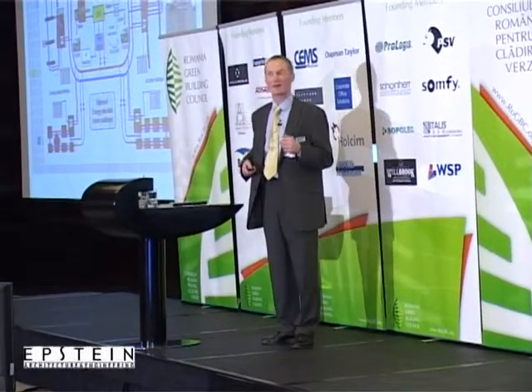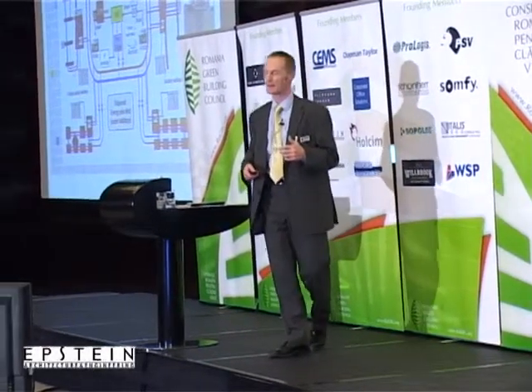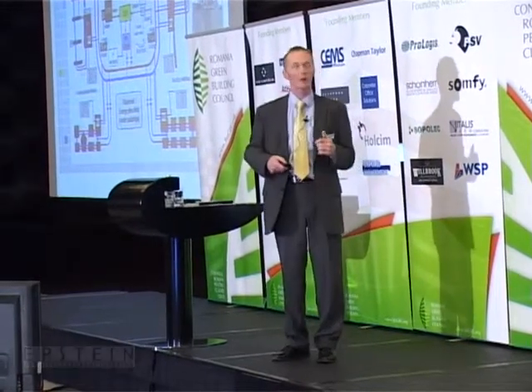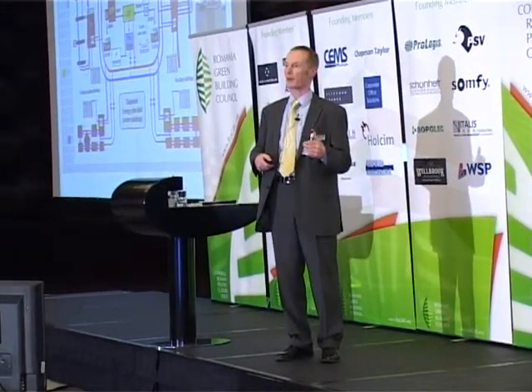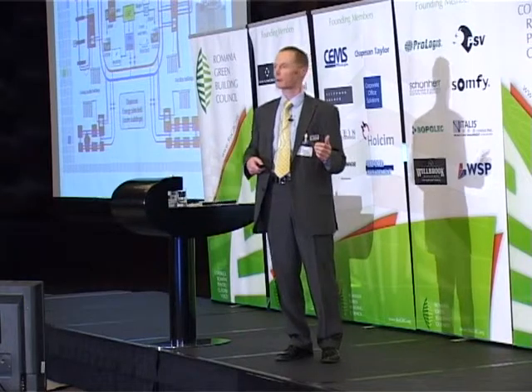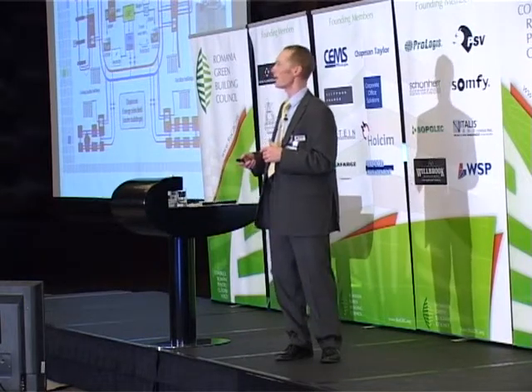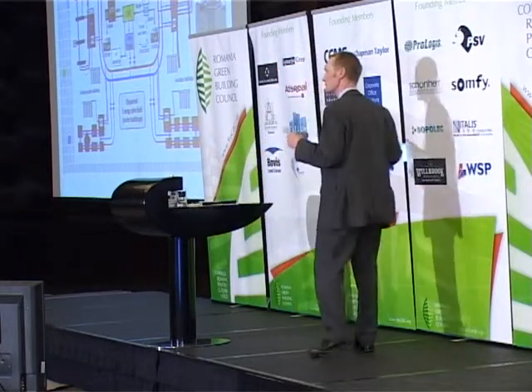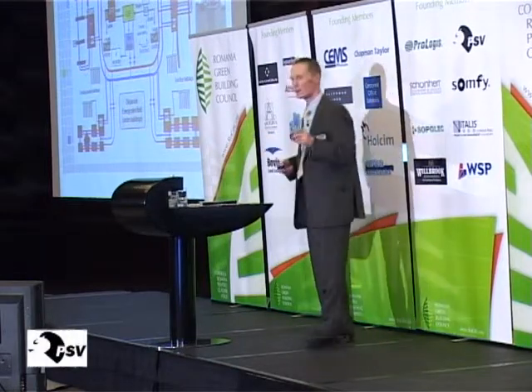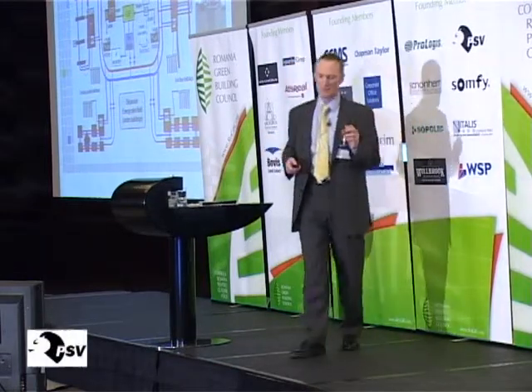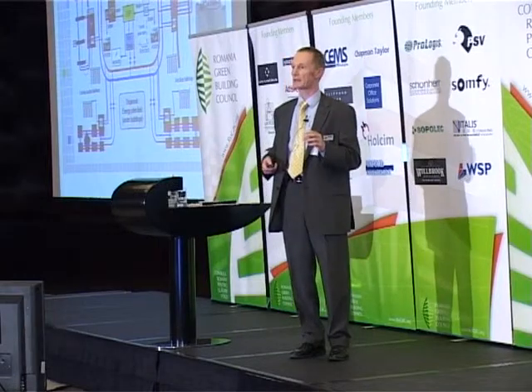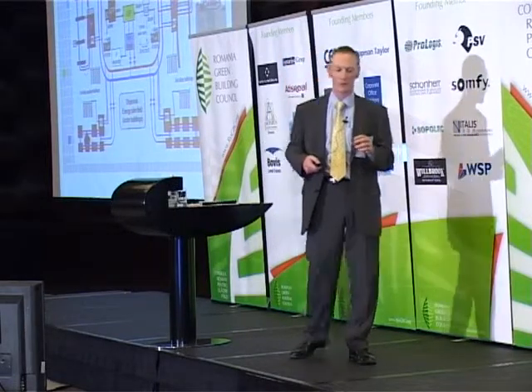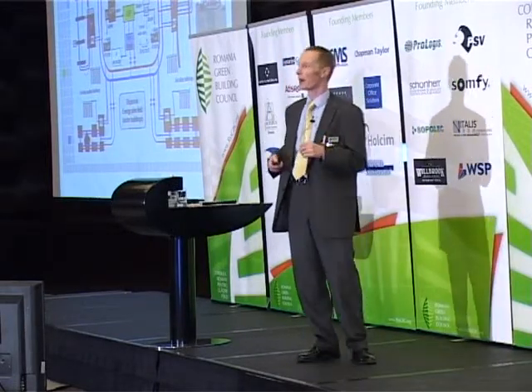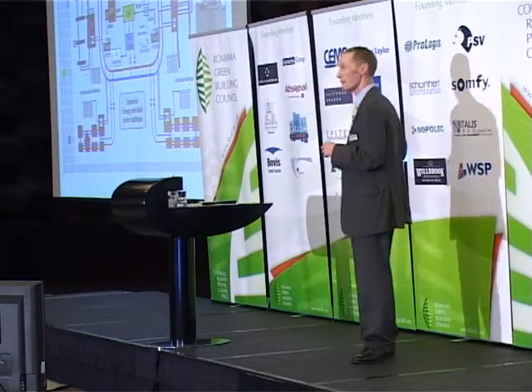Of course, when we actually measured the carbon, what was interesting was that only about 15% of the overall carbon came from heating and cooling the buildings. As mentioned previously by the lady talking about BMSs, we found the residual carbon, about 85%, came from lighting loads and from IT and process loads within the building.